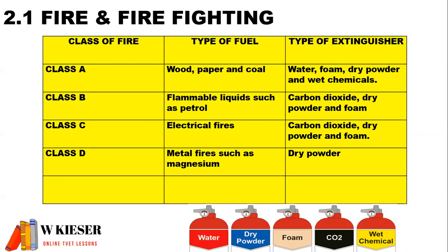For a class D fire, such as metal fires like magnesium, we would use dry powder. For a class K fire, due to cooking fats and oils, the extinguisher we would use is a wet chemical fire extinguisher.